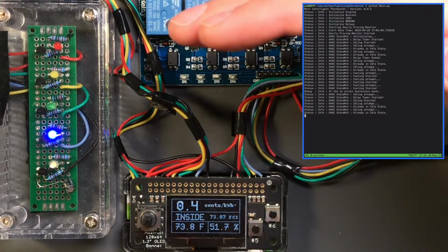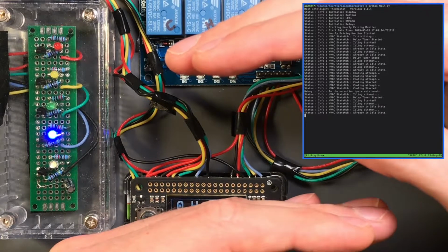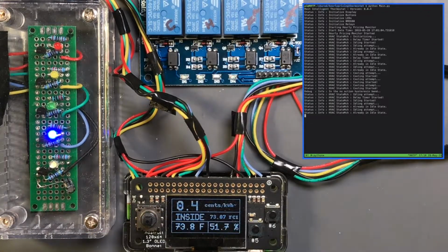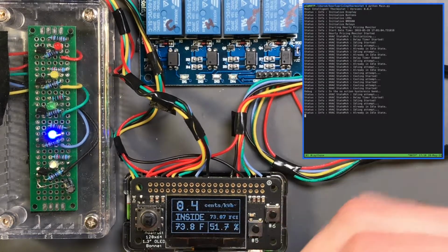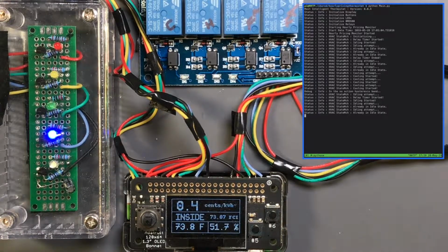So you have your upper limit and your lower limit, there they are, represented by my hands, and you're somewhere in the space in between. That's what I've called a no action hysteresis band. You're just sitting there going, okay, I have nothing to do, and I'm just waiting to hit the lower band or the upper band and attempt to start cooling again.